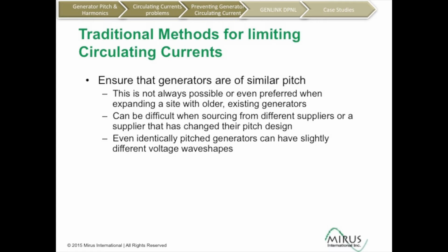So what can we do, or what have we been doing to address this issue? Well, one easy and simple solution would be to ensure that all the generators are of the same pitch. This isn't always possible, however, because if you're connecting on a site that has existing generators, the generator manufacturer may not offer that particular pitch generator anymore. Or you might want to use a different generator manufacturer at the site.